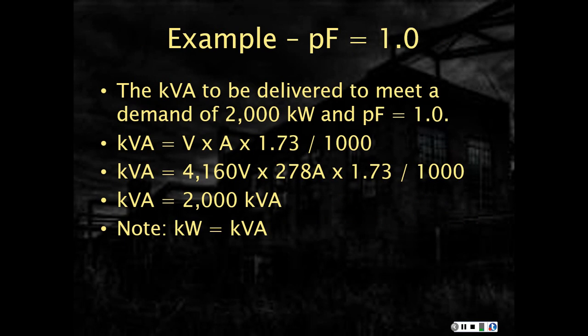Again, let's take a look at an example. The first example is a power factor of 1. The kVA to be delivered to meet that demand of 2,000 kW at a power factor of 1. So this would be what the power company had to deliver to that building in the first example. If I solve for the kVA, volts times amps times 1.73 divided by 1,000, if I run the math out, the kVA is 2,000 kVA. So you should know that works out exactly like we'd expect. kVA equals kW.